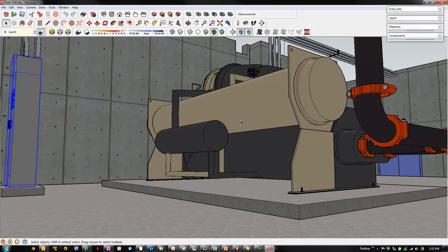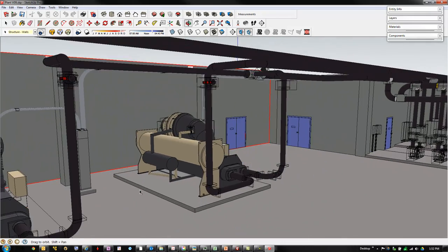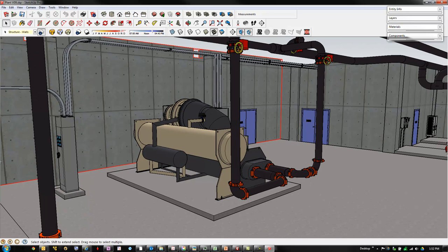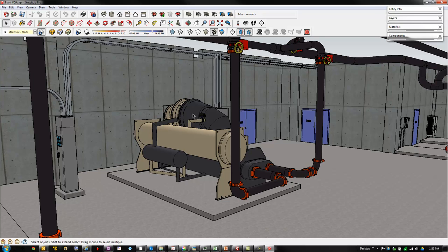So somehow the refrigerant makes its way from the condenser through this line, through this black thing, and can get back to the evaporator, which is what we were looking for, a way back. So now you might be thinking, I wonder what that black thing is. And you have to know a little bit about refrigeration machines to really be able to deduce that. But if you've heard people talk about economizers, or if you took a class in thermodynamics, you may remember that with a multi-stage centrifugal machine, if you can cool the fluid leaving the first stage before it enters the second stage, it can actually improve the efficiency of the machine. And so this is a device that does that.